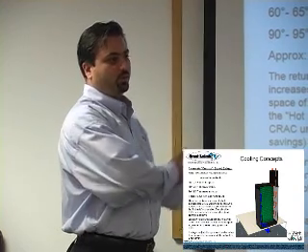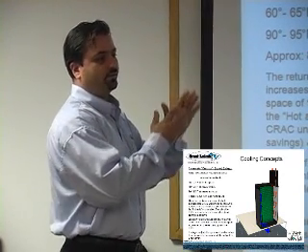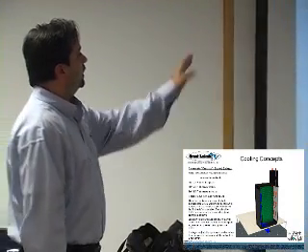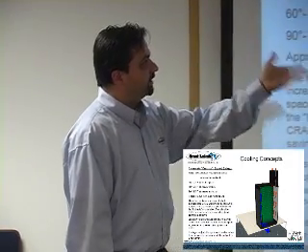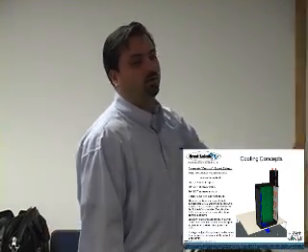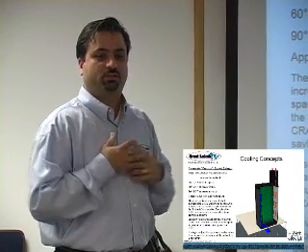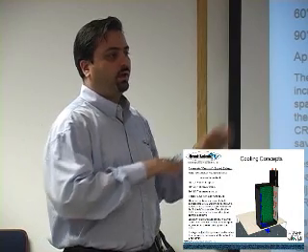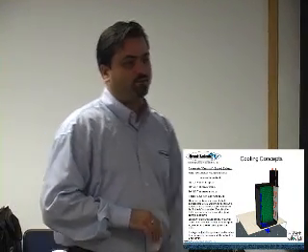It doesn't mix with the ambient room. It actually is ducted right into the enclosure, right to the intake, and still with the same exhaust. You really don't want to go over that too much, and the same method of ducting it out. So now, with this method, there is no hot aisle, cold aisle. You're just cooling the room to where it's suitable for a person, and all the air is ducted through the enclosure. So it's basically part of the HVAC system.